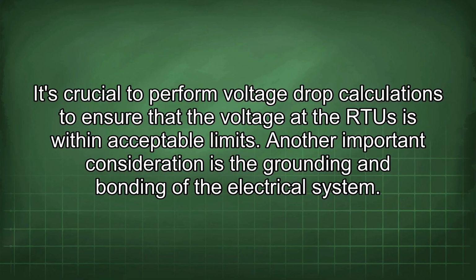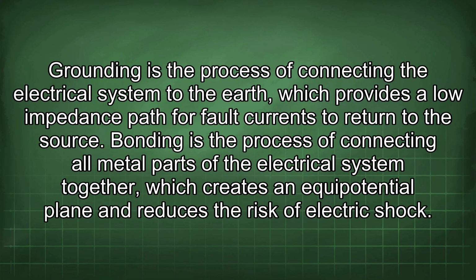Another important consideration is the grounding and bonding of the electrical system. Grounding is the process of connecting the electrical system to the earth, which provides a low impedance path for fault currents to return to the source. Bonding is the process of connecting all metal parts of the electrical system together, which creates an equipotential plane and reduces the risk of electric shock.